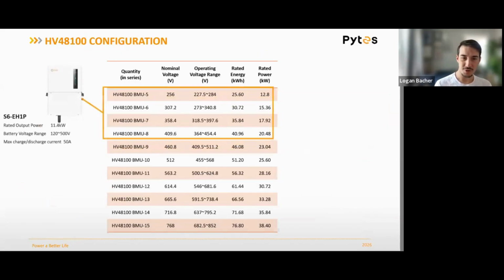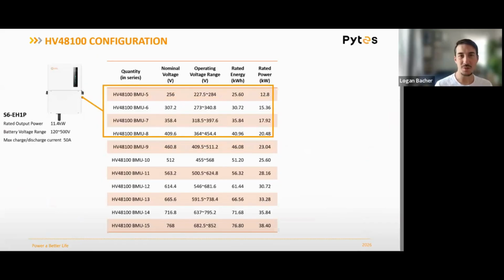When it comes to configuration, this is a big difference between the resi and the commercial stuff: we are connecting the batteries in series. So we need to make sure we have the minimum amount of batteries needed for our equipment, which is that control unit, and the inverter's minimum battery input. But you've also got to be careful that you don't have too many batteries in series, because then you're going to exceed what the inverter can safely accept.